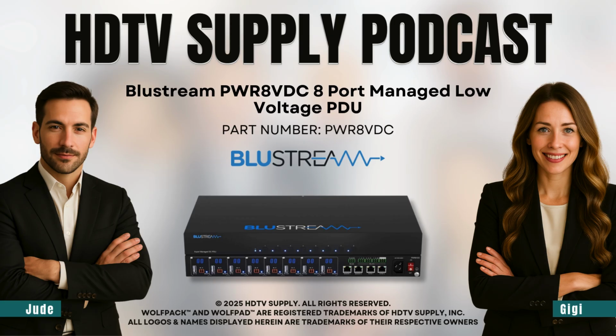Configurable how? That's really the headline feature, the flexibility. Each of the 8 outlets lets you individually select the voltage, 5V, 9V, 12V, 18V, or 24V DC, and each outlet can handle up to 30 watts. Practically, that means you eliminate the mess of wall warts and power bricks, standardizing power right from the rack, which makes cabling and maintenance much simpler.